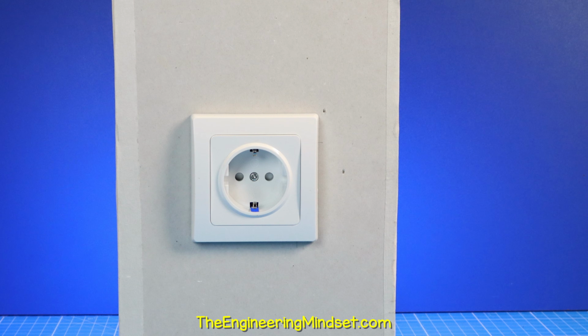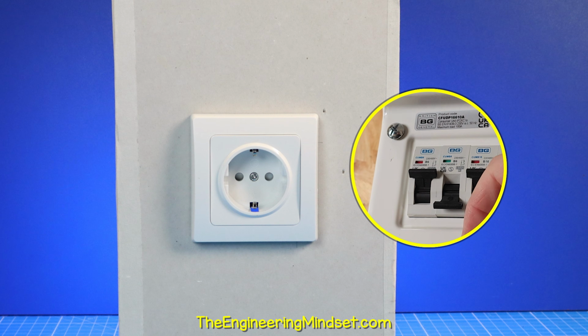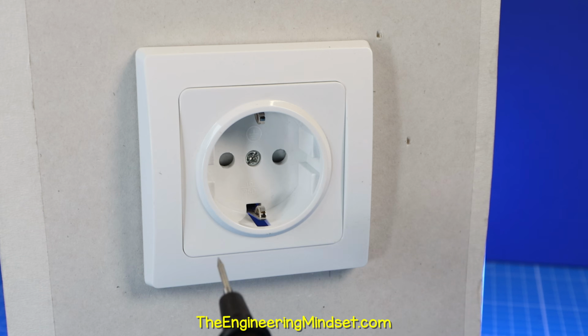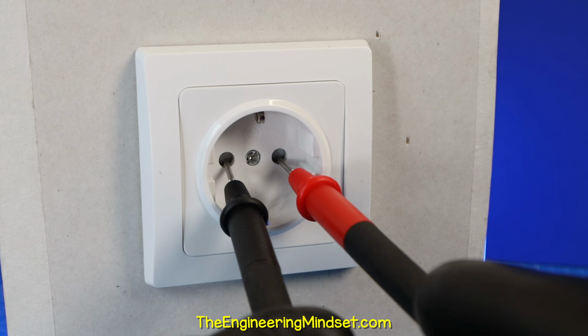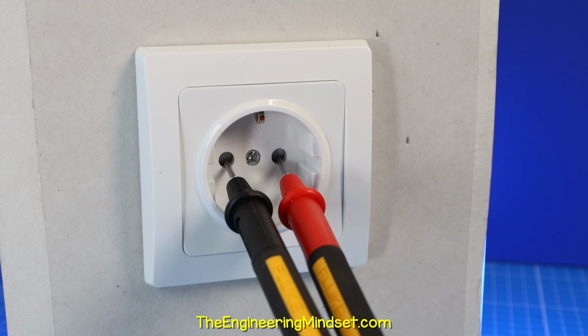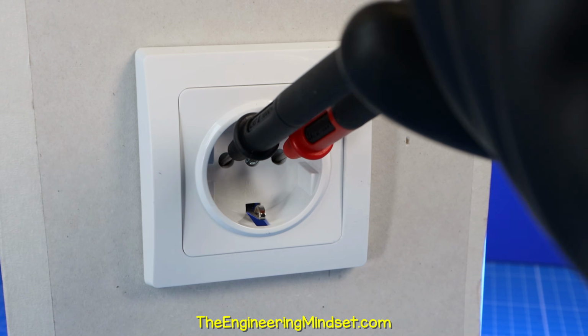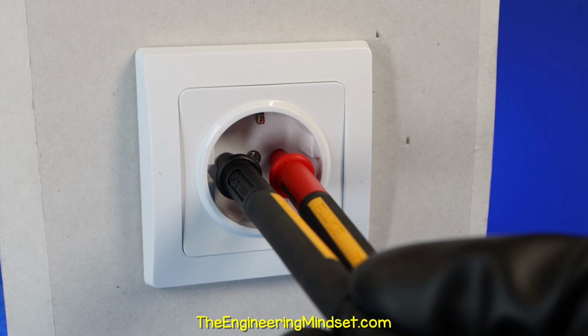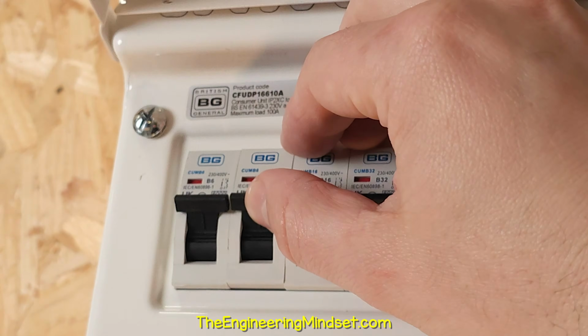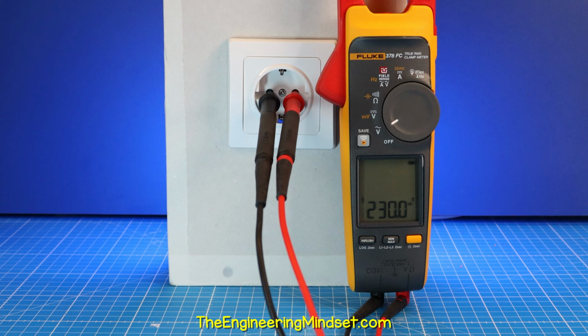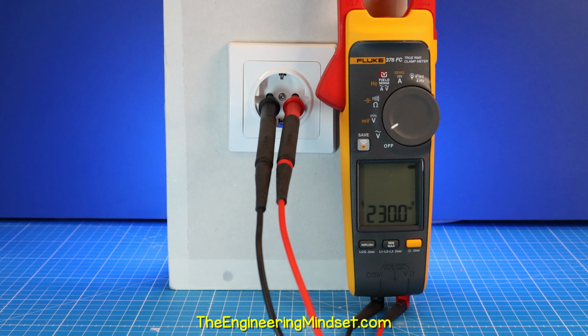For European circuits, I recommend turning the breaker off first where possible. We need to place the leads into the terminals. Apply a light pressure and then tilt the leads to open the safety screen and insert the terminals. When safe to do so, flip the breaker on and the meter will display the voltage value.